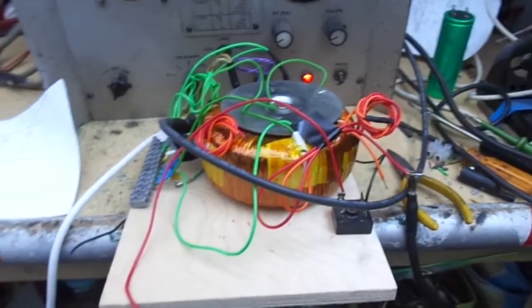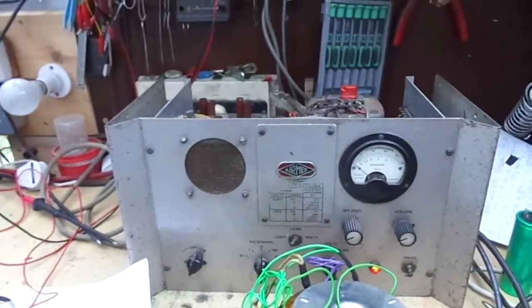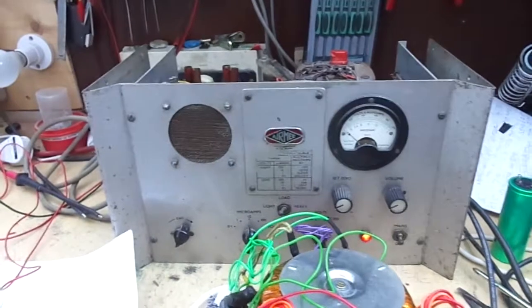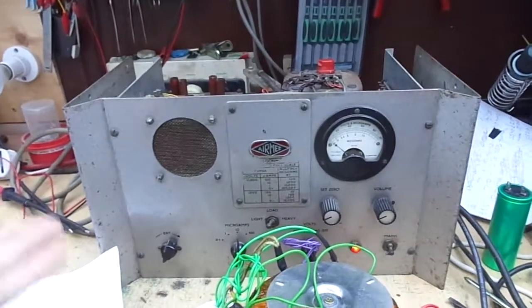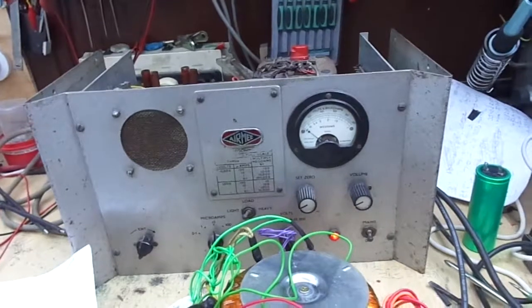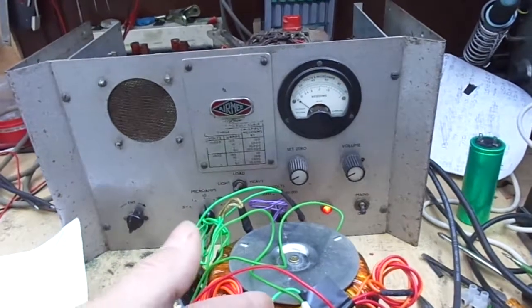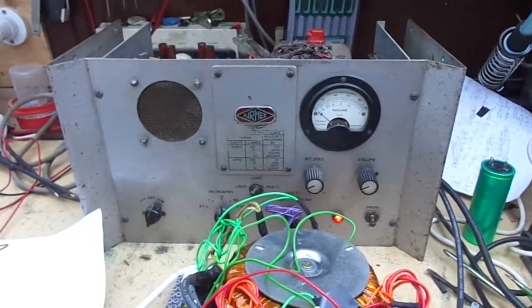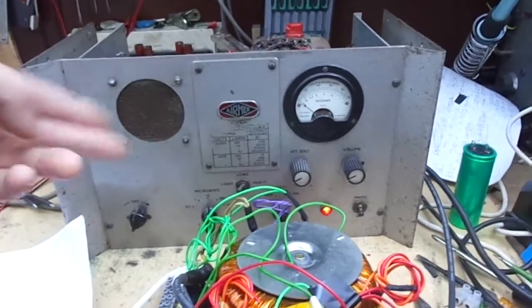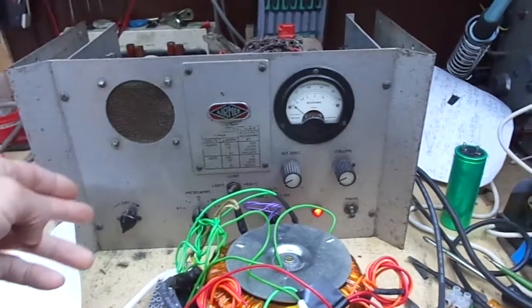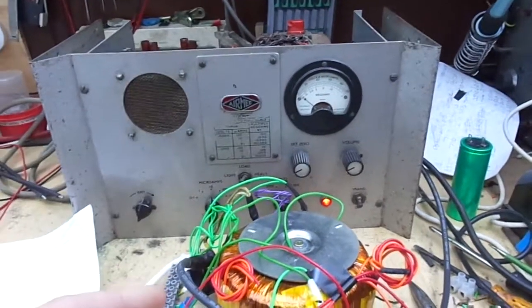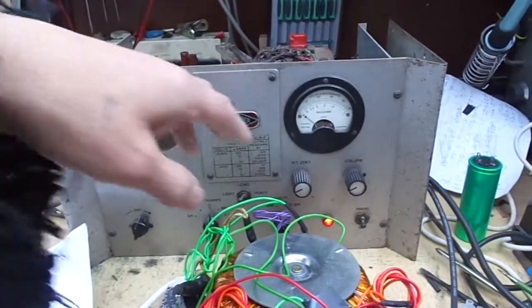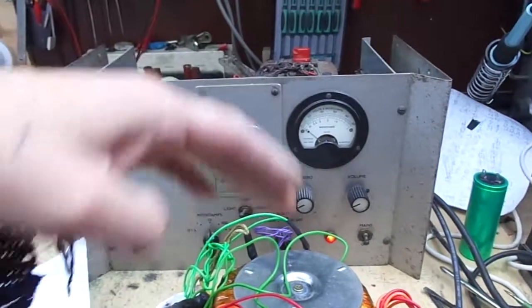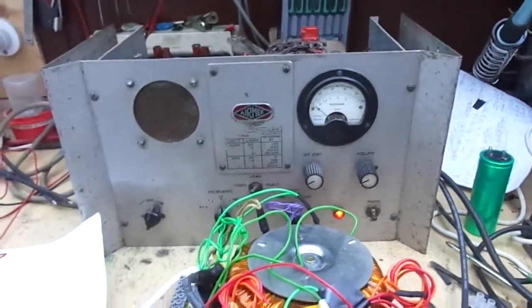So the last test I'm going to do is using this old Airmec insulation tester, and basically it's a megger, so it tests the insulation resistance of anything, a capacitor or whatever. What it does is put in a very high voltage, either 1000 or 10,000 volts variable, and basically it's listening to the insulation. It's got an amplifier, you'll see in a minute.